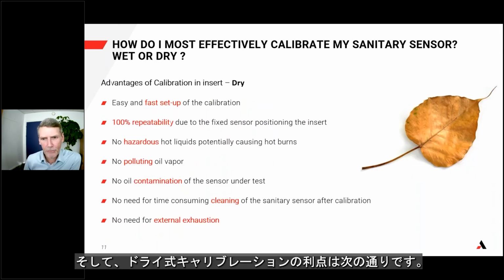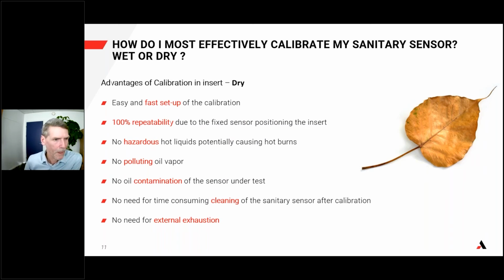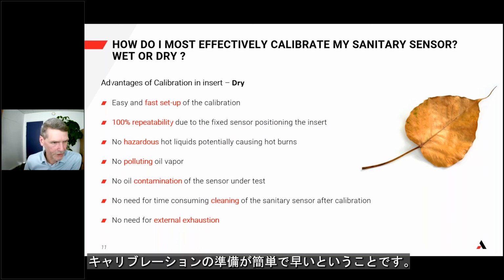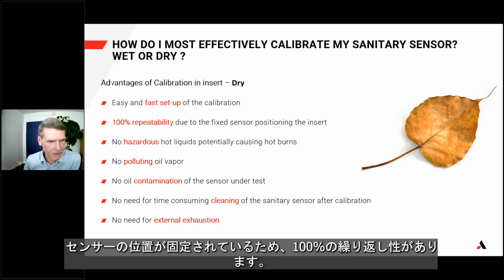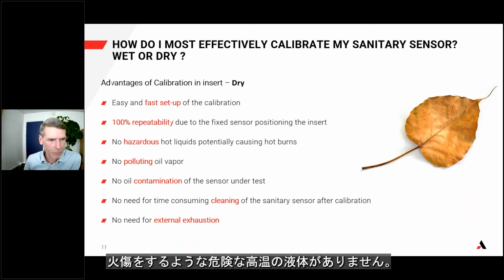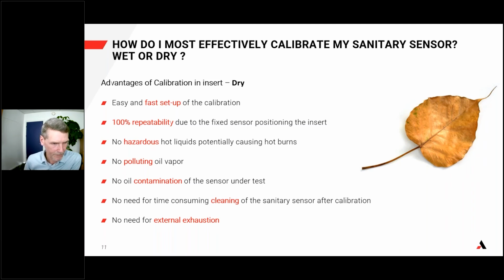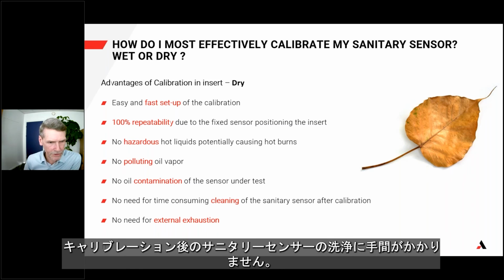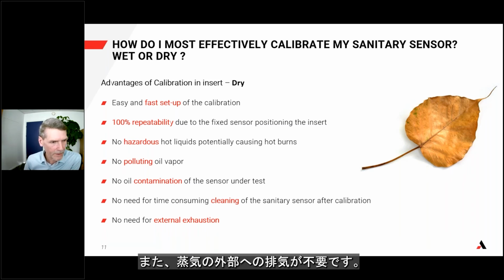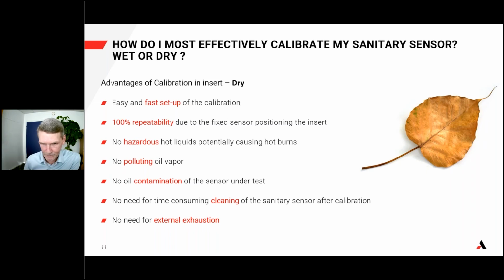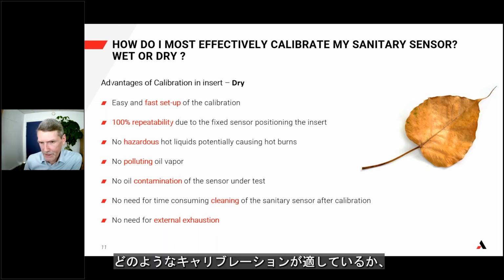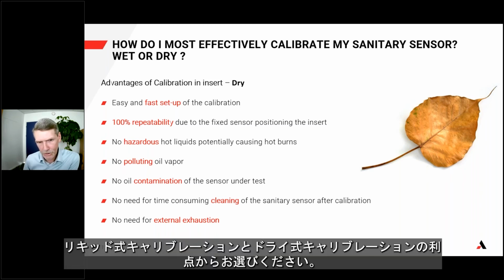And here is a list of the advantages for dry calibration. Easy and fast setup of the calibration, 100% repeatability due to the fixed sensor positioning in the insert, no hazardous hot liquids potentially causing hot burns, no polluting oil vapor, no oil contamination of the sensor under test, no need for time-consuming cleaning of the sanitary sensor after calibration, and no need for external exhaustion. Now with these lists of advantages for both wet and dry calibration, you can choose what calibration would suit you the best.